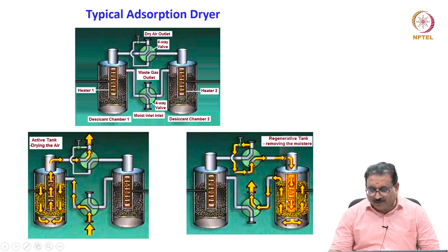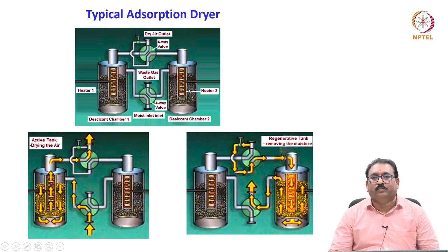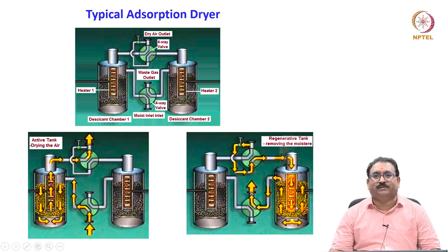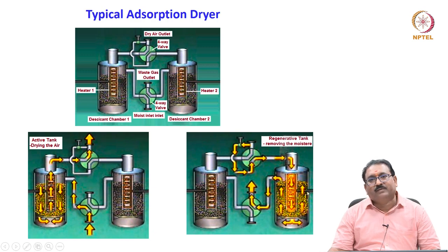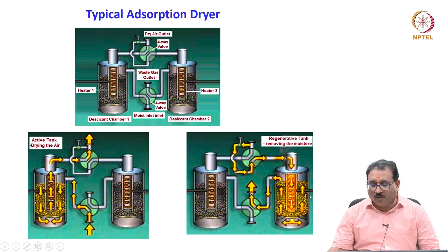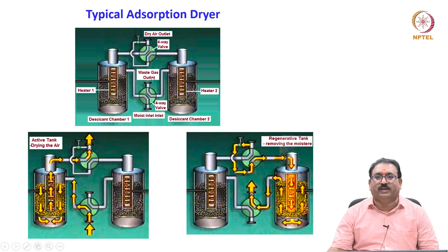Please note that heaters are provided in each desiccant bed — heater 1 and heater 2 — and these heaters are on only when regeneration is taking place. The active tank dries the compressed air and the other is used for regeneration, meaning removing the already contaminated bed. The middle outlet is the waste gas outlet through which hot air exits. The moist air inlet and dry air outlet are on the sides, while the middle one is used for the waste gas outlet.